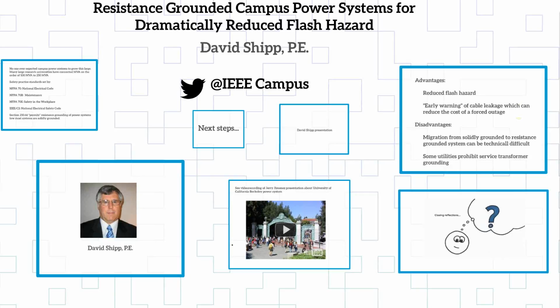So if I get a ground fault and I have 20,000 amps of fault current, a couple hundred feet of cable to the conduit, you're not just pulling new cable. You're at $75 per foot. It's going to be $50,000 to $75,000 every time I replace a few hundred feet of cable that's burned up in the conduit or the raceways or so on. And when it fuses to the conduit, sometimes you have to replace the conduit with it. I've been into a few cases where that's been the situation.